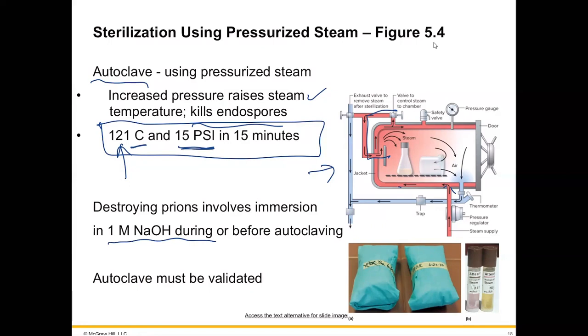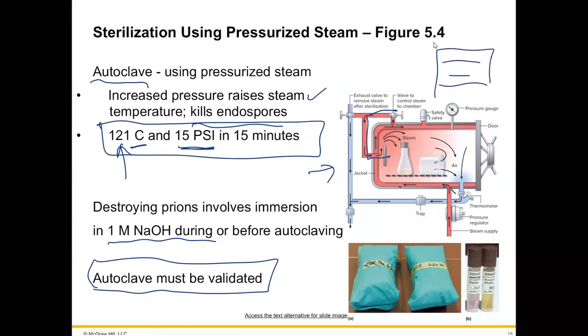Okay, now the autoclave has to be validated. You have to prove that the autoclave is heating up to the required temperature in all of the spots in it, right? If you think about your oven at home and how it might get hotter in one area compared to another, that's not validated. That would not be good enough for an autoclave. The autoclave has to be heating up to 121, and the pressure has to be 15 throughout the autoclave. Some people have gotten sick because the autoclave has had a cold spot or something.